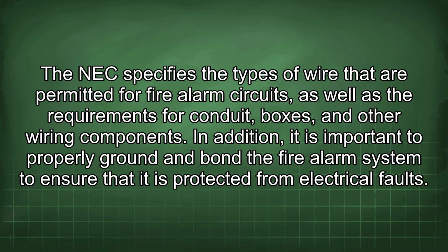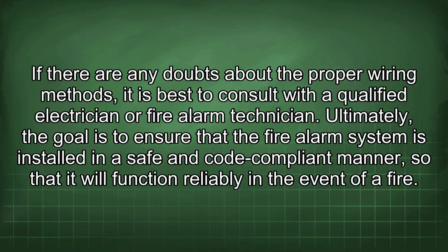The NEC specifies the types of wire that are permitted for fire alarm circuits, as well as the requirements for conduit, boxes, and other wiring components. In addition, it is important to properly ground and bond the fire alarm system to ensure that it is protected from electrical faults. If there are any doubts about the proper wiring methods, it is best to consult with a qualified electrician or fire alarm technician. Ultimately, the goal is to ensure that the fire alarm system is installed in a safe and code-compliant manner, so that it will function reliably in the event of a fire.